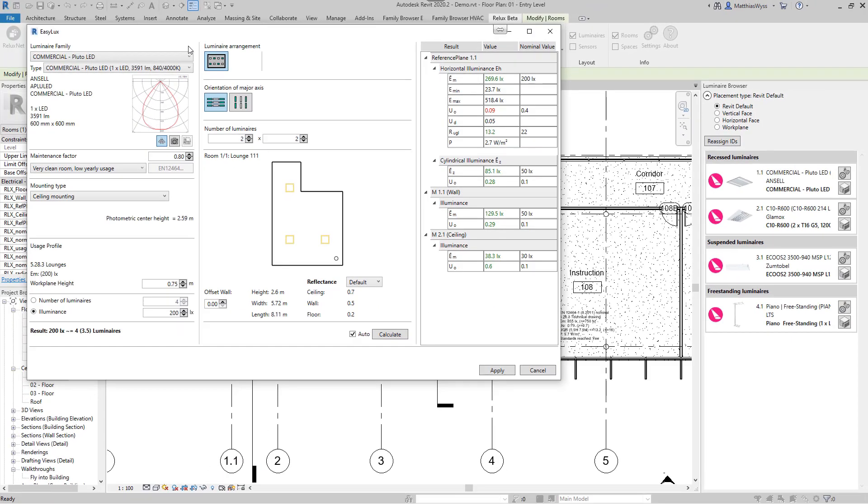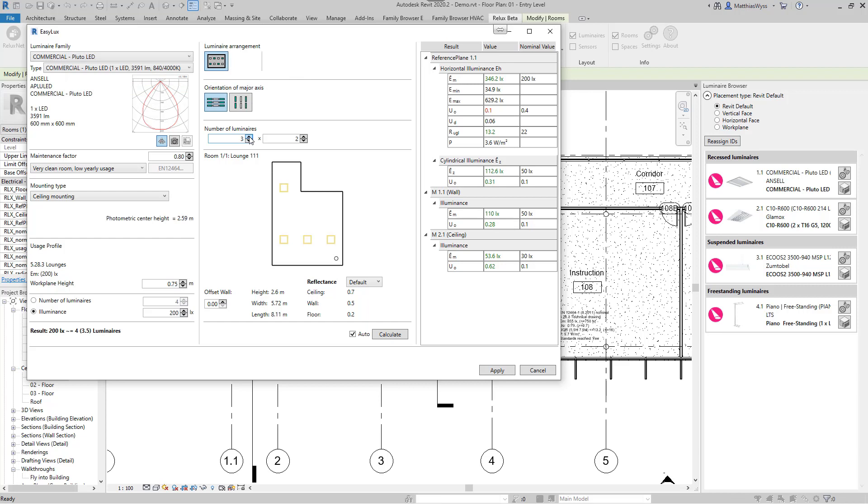We can now correct this by selecting a different luminaire, adjusting the number of luminaires, or adjusting other parameters. If automatic calculation is activated, the results will be updated with each change, so we will get to the correct result in a short time. This option can be disabled so that we can set the parameters freely and then start the calculation manually.